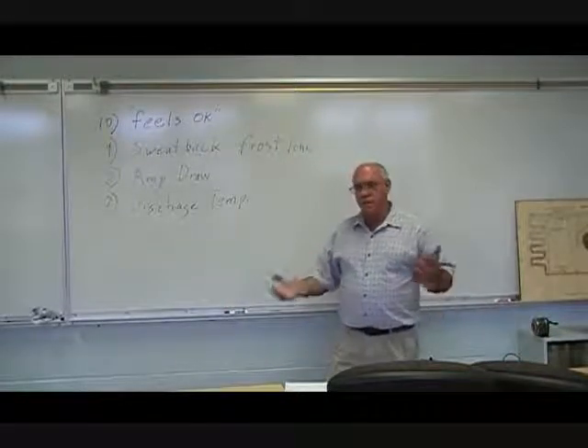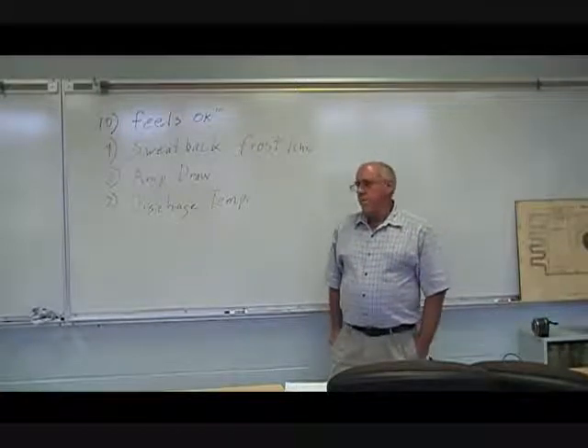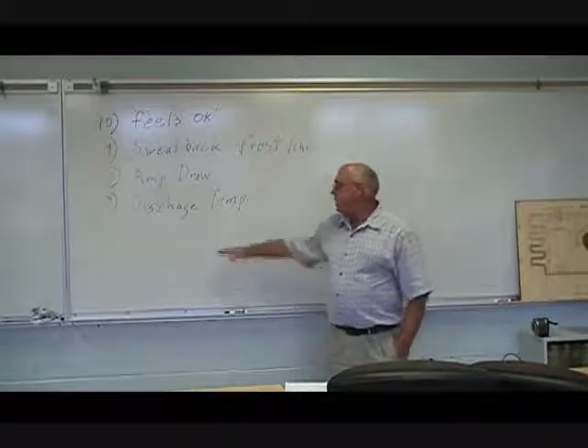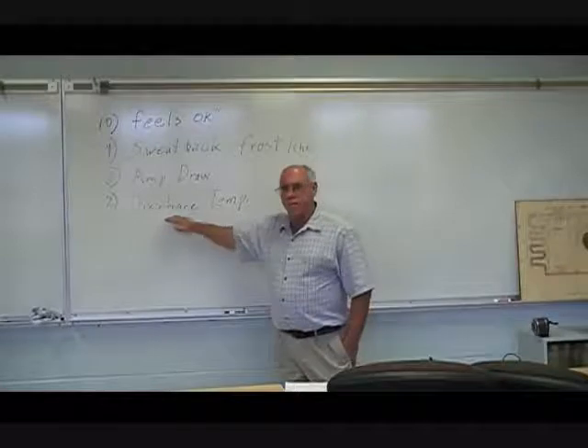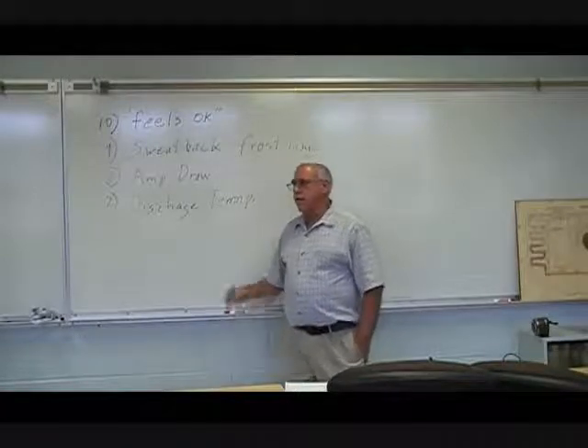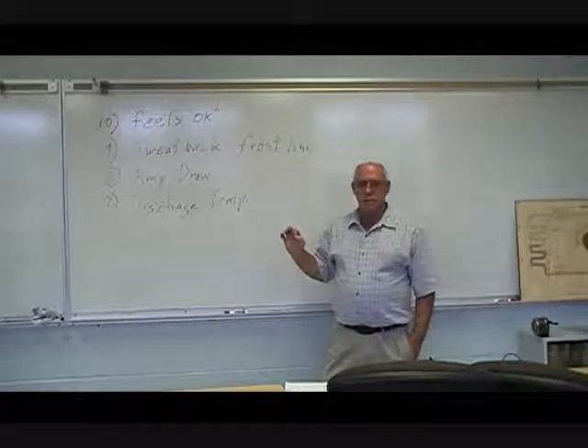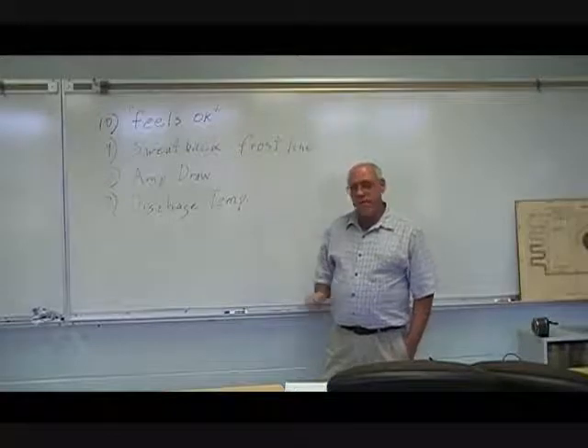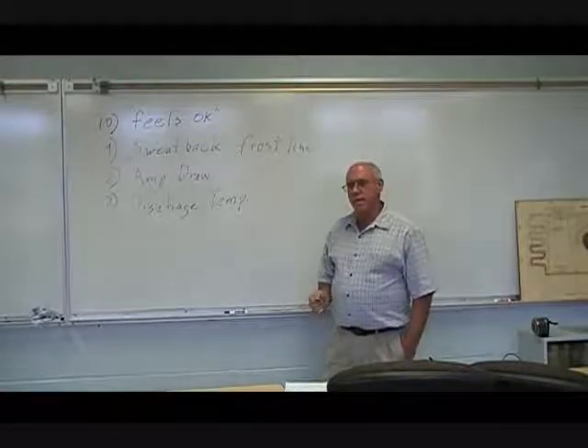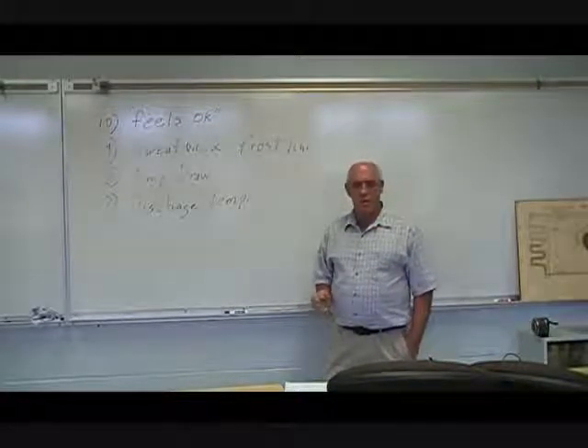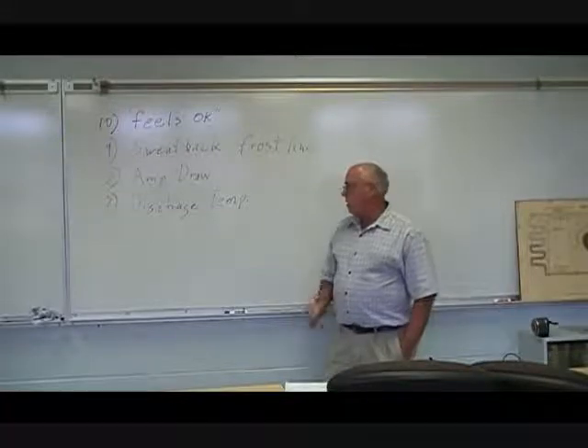Give or take a few degrees. If it's 60 degrees outside, I would expect to see a discharge temperature around 160. Is that a way to charge the system? It'll get you by, but it's not the best way by any means.